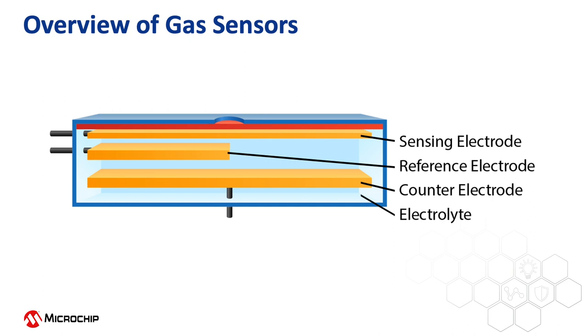Both two and three terminal electrochemical gas sensors are in use today. A three terminal gas sensor is shown here, consisting of a sensing electrode, a reference electrode, and a counter electrode. A two terminal sensor functions the same way but does not have a reference electrode.